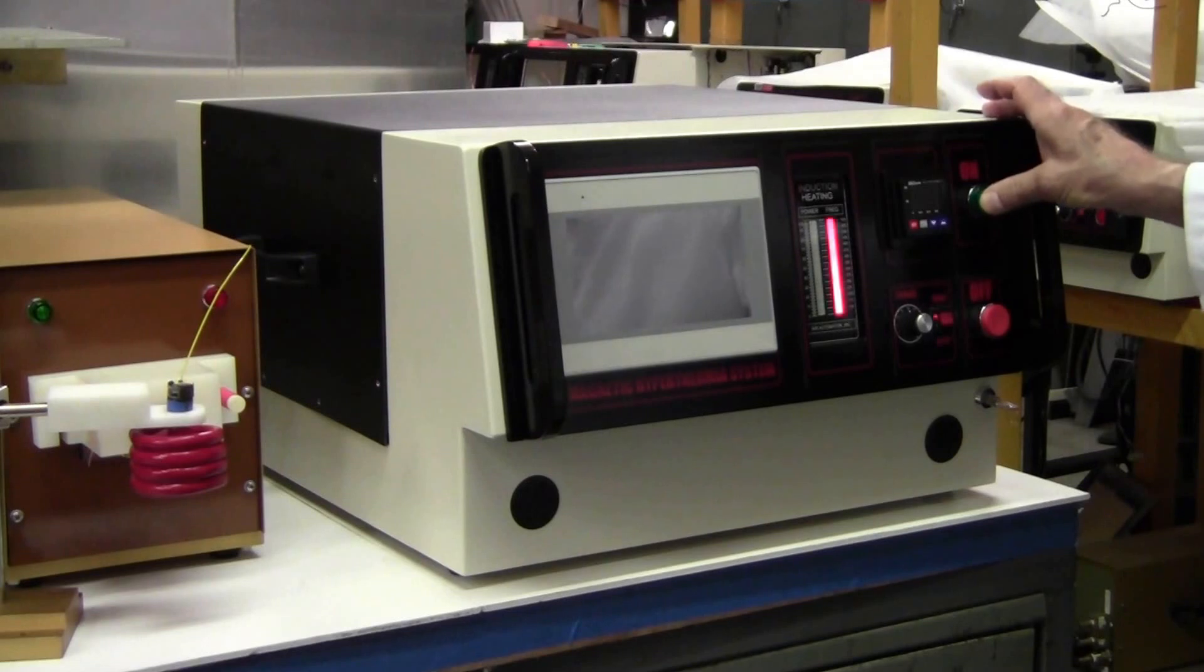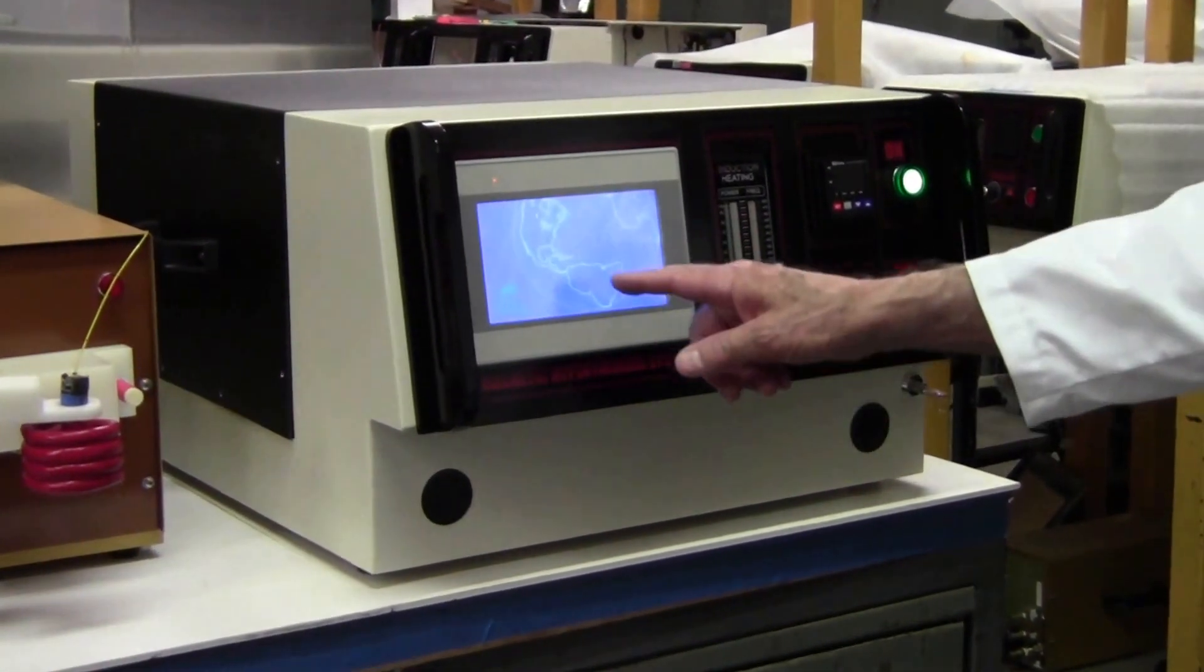This is an MSI automation magnetic hyperthermia instrument, and what we'll be demonstrating is heating and some of the controls that you have. I'll press the green button and that turns on the machine. Now it will go through a startup procedure. First, it'll turn on the color touchscreen.